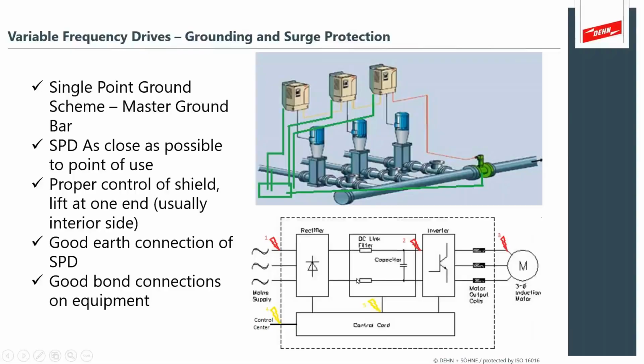So what does this look like with industrial control and process control? You want equipment to have its own dedicated bond back to a master ground bar. You want the valves to have lightning protection and be properly grounded. For cathodic control systems, they're floating, so you need to make sure you're watching what's grounded and what's not grounded. But what's important is that they have dedicated runs back to the single point master ground bar. The SPDs are as close as possible next to the variable speed drives. Proper control of the shielding is usually lifted at what's considered the control cabinet, but that's a big discussion of its own. Good earth connection systems to the actual master ground bar, and good bond connections on the equipment, where the pumps and the valves have obvious and secure bonds.